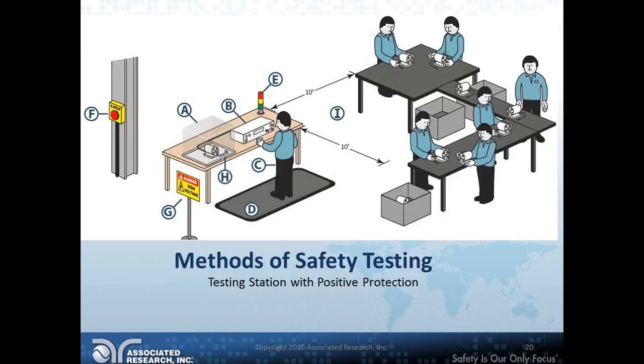So that's something you really should keep in mind. If OSHA came in and looked at a station and saw there wasn't a 10-foot separation, no PPE, and the people at the other station weren't even aware there was HIPOT testing within that 10 feet, you could get dinged for that, and I've seen it happen. But we also realize the best way to make sure you have true protection is something like an enclosure.